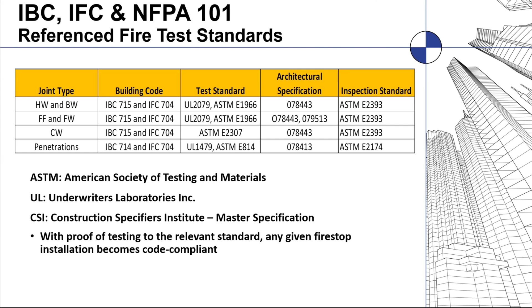The joints, which would be head of wall, floor to floor, and curtain wall, all have very similar standards. Curtain wall has a separate test standard; it uses ASTM E2307. Then penetrations, where they puncture holes in the structure to allow utilities, have their own test standards, UL 1479 and ASTM E814, and that is specification section 078413. It has its own inspection standard, which is different from the joint standard: ASTM E2174. So all of these entities work together to ensure that the structure is designed to meet all of the standards required to make it a safe structure.